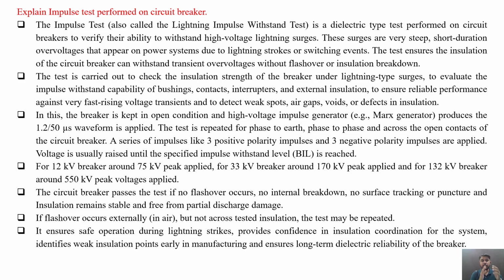In this, the breaker is kept in open position. The high voltage impulse generator, that is the Marx generator, produces the 1.2/50 microseconds waveform, which is the standard impulse waveform, and it is applied. The test is carried out or repeated for phase to earth, phase to phase and across the open contacts of the circuit breaker. A series of impulses, like 3 positive polarity impulses and 3 negative polarity impulses, are applied.